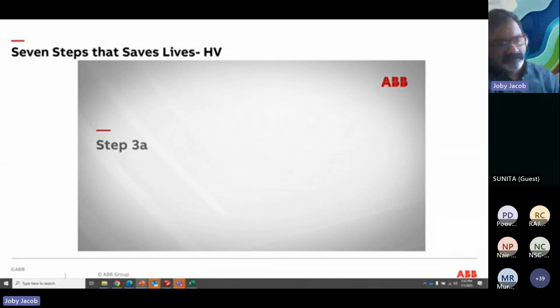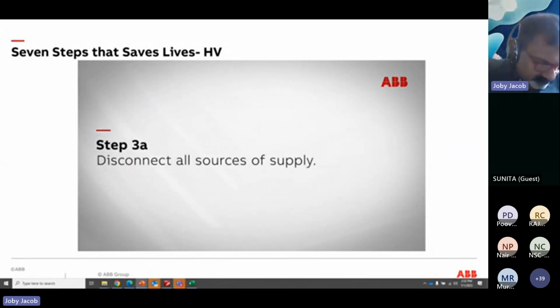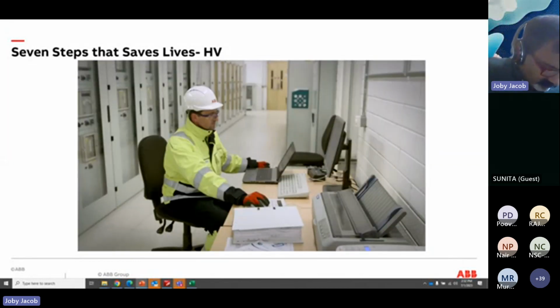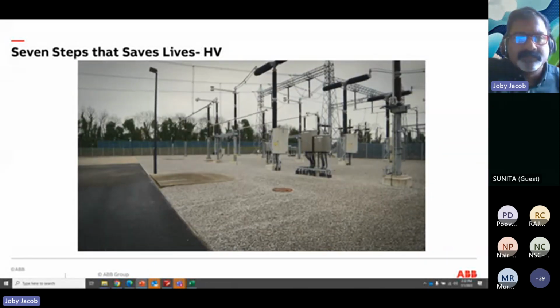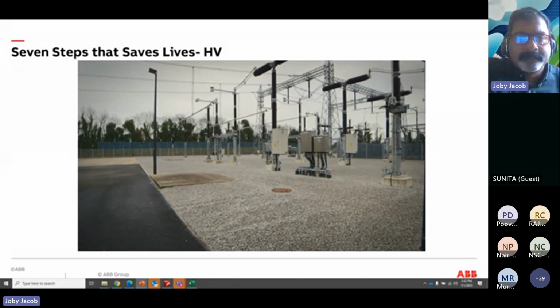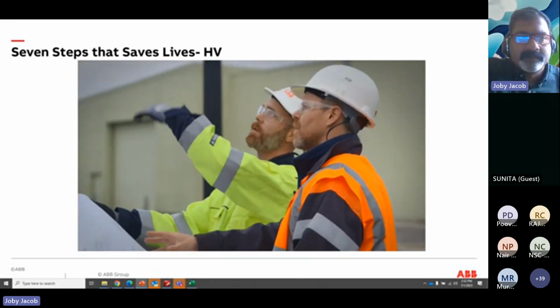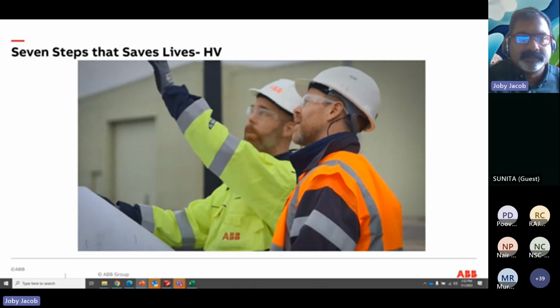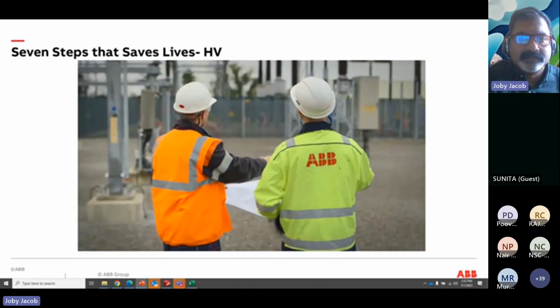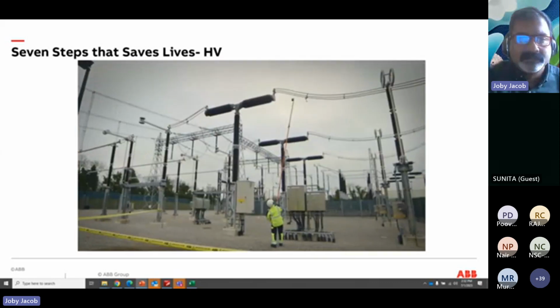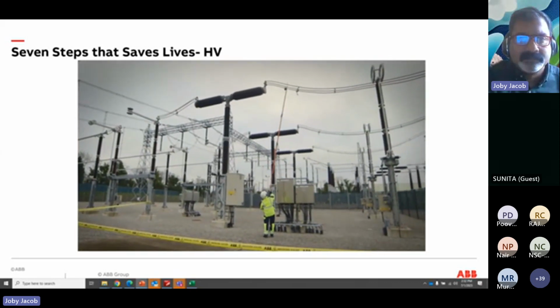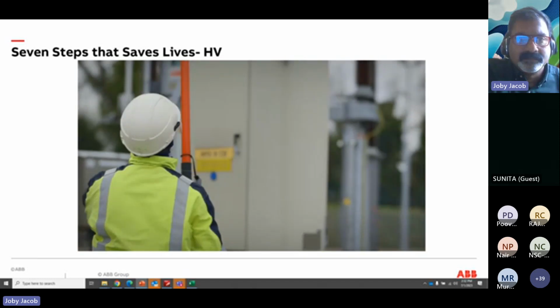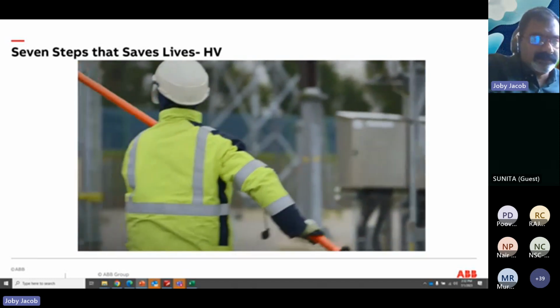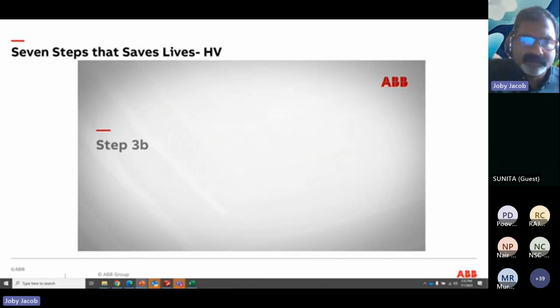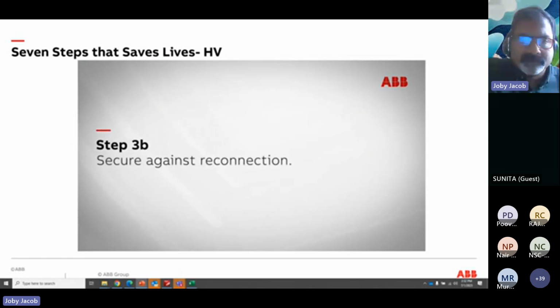Step 3A. Disconnect all sources of supply. Where possible, ABB recommend that switching should be conducted remotely. If not, observe switching from a safe distance well beyond the ARC Flash boundary. If switching is performed prior to arrival, walk down the equipment to check the isolation points upon arrival. When required, perform switching only if properly trained and while wearing the proper PPE identified in Step 1. Step 3B. Secure against reconnection.